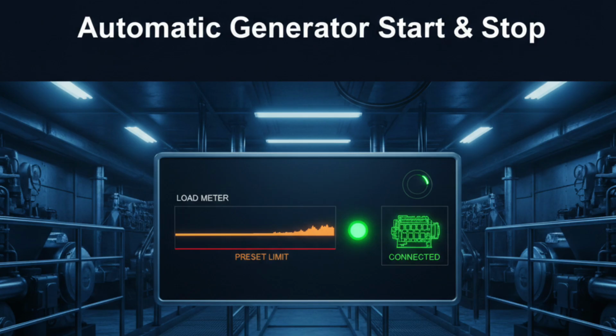When the system detects that the total load exceeds preset limits, it starts a standby generator without any manual intervention. Once the generator reaches the correct voltage and frequency, PMS synchronizes it to the busbar and shares the load automatically with other running generators. When the total load decreases, PMS stops one or more generators to save fuel, reduce wear, and maintain efficiency. This automation ensures continuous, uninterrupted power supply to critical systems, including steering gear, emergency lighting, navigation systems, and fire pumps. It also helps operators manage multiple generators without constantly monitoring them manually. Proper operation of automatic start-stop improves fuel efficiency, reduces human error, and ensures operational safety under sudden load changes.